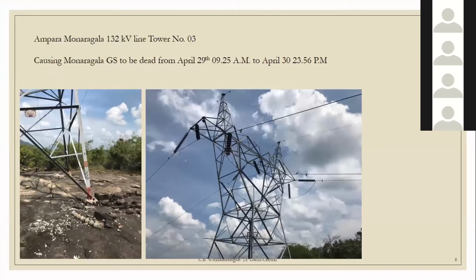And this is the latest incident which we faced in our transmission line network. This happened on April 29th. The Monaragala GS was dead due to the tripping of the Ampara Monaragala transmission line at 9:25 a.m. And then we had to find what the cause was. After finding the cause, it was at tower number 3, insulator flashing over. We found the place, then we replaced the insulators, then we were able to re-energize the Monaragala grid the following next day in the afternoon. So as you can see, it's almost 2 days the Monaragala GS was dead.